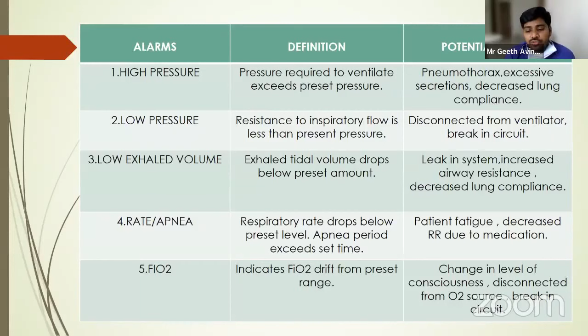For rate and apnea, the respiratory rate drops below the preset support. It depends on the settings we have kept; if the patient is not maintaining or reaching that, there will be a rate or apnea alarm. The apnea alarm sounds when the apnea period exceeds the set time. Potential causes are patient fatigue, or decreased respiration due to medications, such as more anesthesia or sedation. The FiO2 alarm indicates FiO2 drifting from the preset range. Potential causes are a change in level of consciousness, disconnection from the O2 source or sockets, and a break in continuity of the circuit.